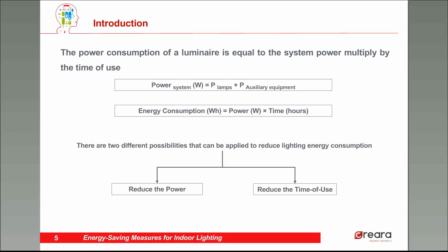The energy consumption of a luminaire is equal to the system power times the time of use. The system power is the power of the lamps plus the power of the auxiliary equipment. This system power times the time of use is the energy consumption of my lighting system. Based on this formula, there are only two ways we can reduce the energy consumption: reduce the power, or reduce the time of use.